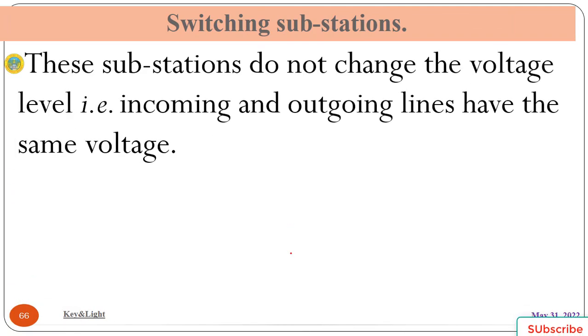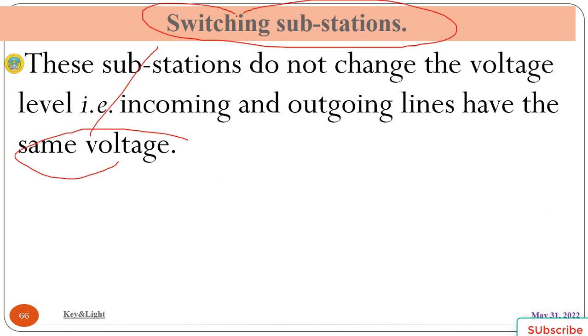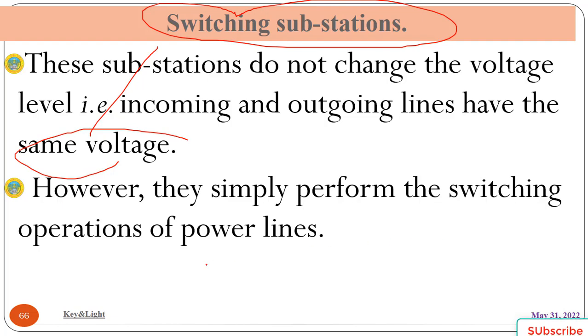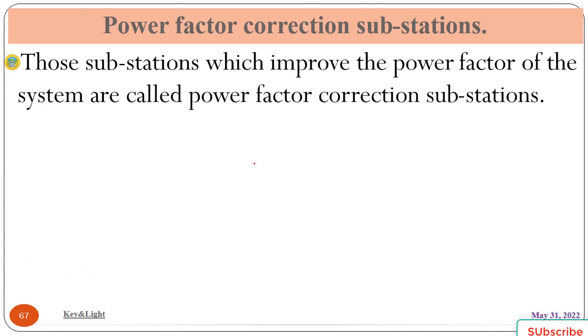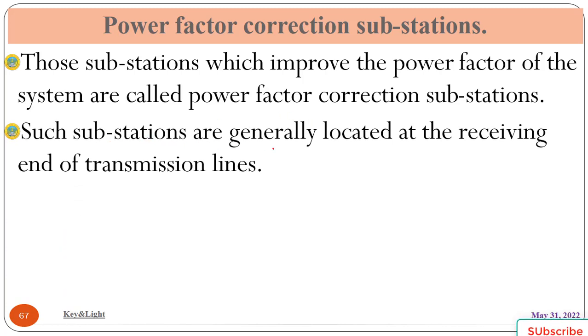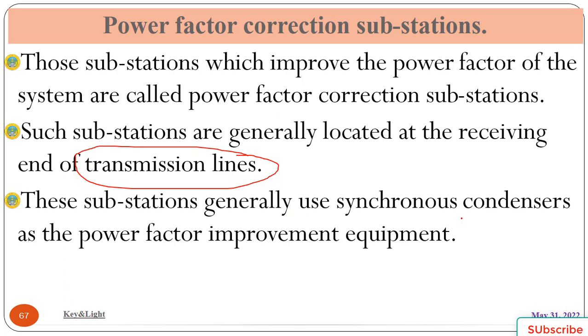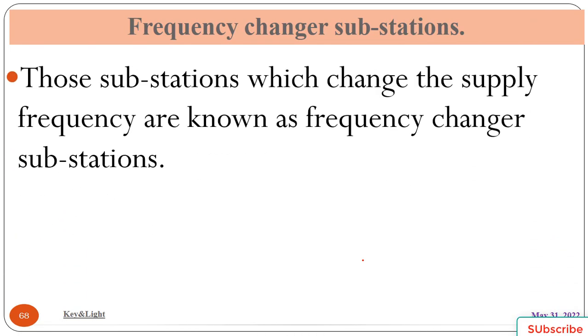The other one is switching substation. These substations do not change the voltage level; incoming and outgoing lines have the same voltage. As the name indicates, the switching substation function is only switching off and on. They simply perform the switching operation of power lines. The next one is power factor correction substations. Those substations which improve the power factor of the system are called power factor correction substations. Such substations are generally located at the receiving end of a transmission line to correct the power factor. These substations generally use synchronous condensers as the power factor improvement equipment.